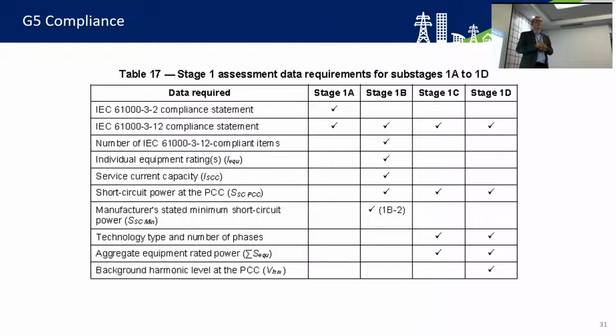So what you're finding is people are coming along saying, I want to connect 3 or 4 of these 50 kilowatt EV chargers. And we're coming along saying, well, here's a HV point to connect. Whoa, I don't want a HV point connection - I don't want to spend 80 grand on putting a new sub in for these chargers, which commercially nobody wants to do, because it makes the job unviable, financially not viable.